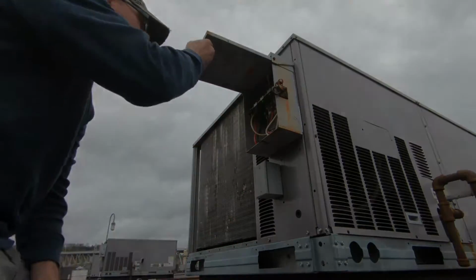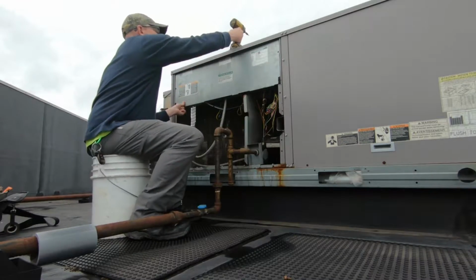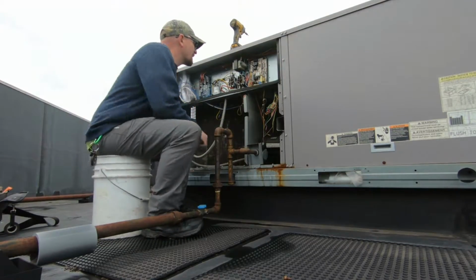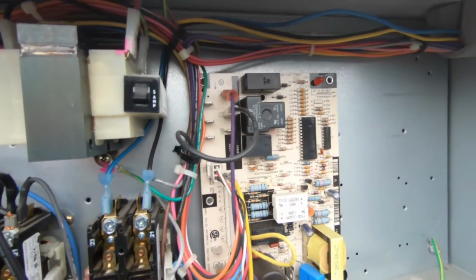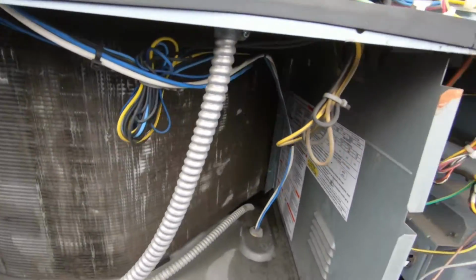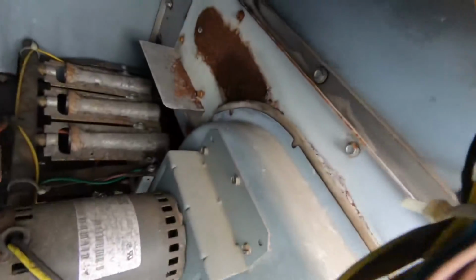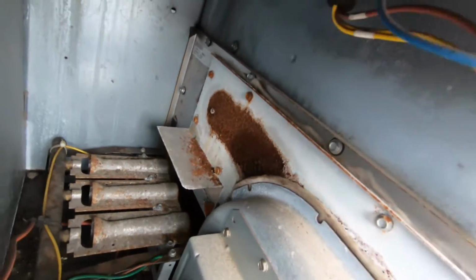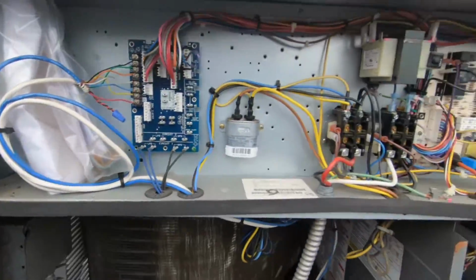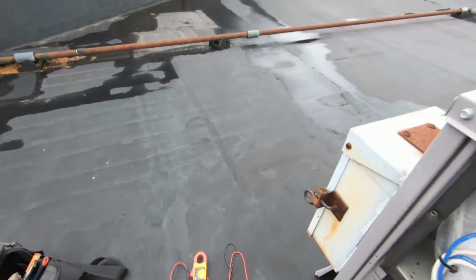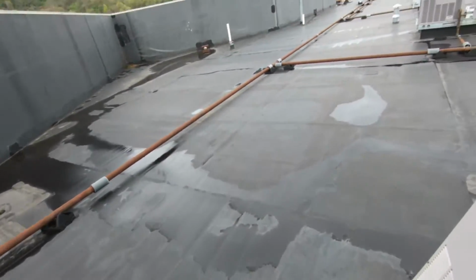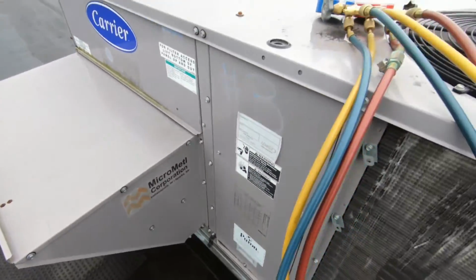Well, it looks like this is our unit. Maybe it's got a bad compressor. Who knows? Maybe somebody just turned the breaker off for no reason. But we're gonna find out. All the electrical looks pretty good. Contactors are a little pitted, a little bit burnt. I'll probably write those up to have them replaced. Heat exchangers looking pretty rusty here on the front plate, so we're definitely going to give that thing a good look. I'm going to go ahead and open up that compressor compartment and see if the system's got refrigerant in it, and I'm also going to test the compressor, make sure it's not shorted out, shorted to ground or anything.